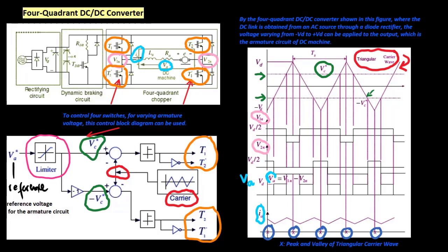The frequency of current ripples in the armature winding is twice the switching frequency, or twice the carrier frequency. Hence, by increasing the switching frequency, the torque ripples and acoustic noise due to the current ripples can be reduced. In particular, if the switching frequency is above 10 kilohertz, then audible noise from the DC machine can be perfectly eliminated.